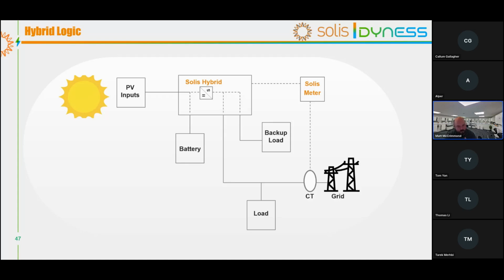So that only is possible if the capacity of the battery is low enough for you to be able to put that energy in. But for example, if it was 100%, then the inverter would clip the PV energy. So we do have customers ask sometimes when they look on Solis Cloud why their generation curve is much higher than what the rated nameplate of the inverter is, and that's the reason. It's because you can actually charge on the DC side straight to the battery. So it's a DC charging circuit, as the diagram explains there. Hopefully that kind of clears up maybe some of the questions that end users might ask you in terms of the monitoring, because I know that that's sometimes a big thing.